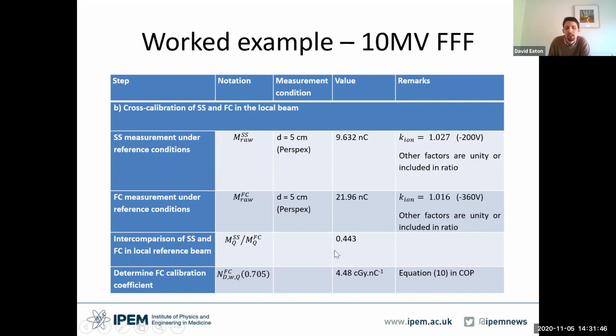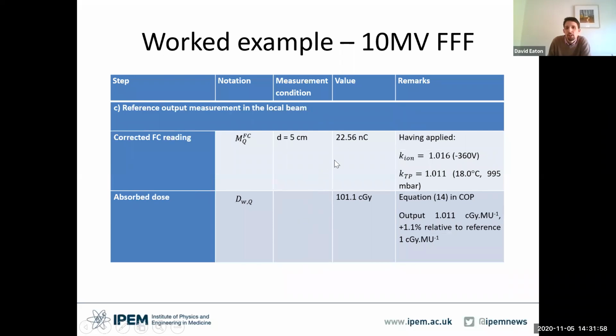So we'll get an intercomparison or cross calibration ratio, and then we can use that, using the equation I showed you, to give a calibration coefficient for our field chamber. We then take our field chamber reading where we've applied the ion recombination and the temperature pressure correction for the particular setup, and then we get a dose to water at the end. So in this example, it's come out as 101.1 centigray for 100 monitor units. So that's 1.1% higher than our standard reference. And we may choose to leave that, we may choose to bring it closer to unity.